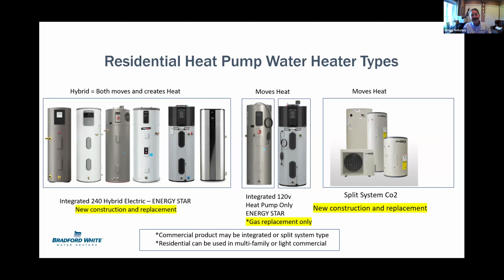When you put a heat pump-only model in, you have to follow the manufacturer's instructions for how many people can be in the house, and set the right expectation that recovery takes hours, not a short period of time, because you don't have that 4,000-4,500 watt heating element. There are proper applications for those, but you have to follow what the manufacturer says, because their name is on the line if it goes into a house with 6 people used to a tankless water heater, and now they get nothing close to that recovery.